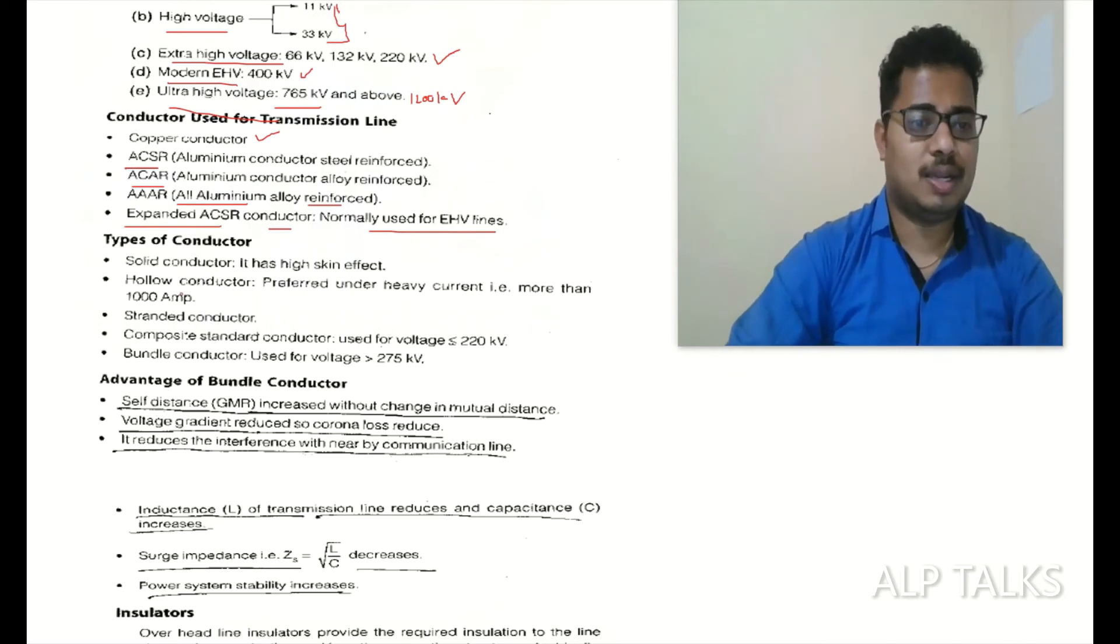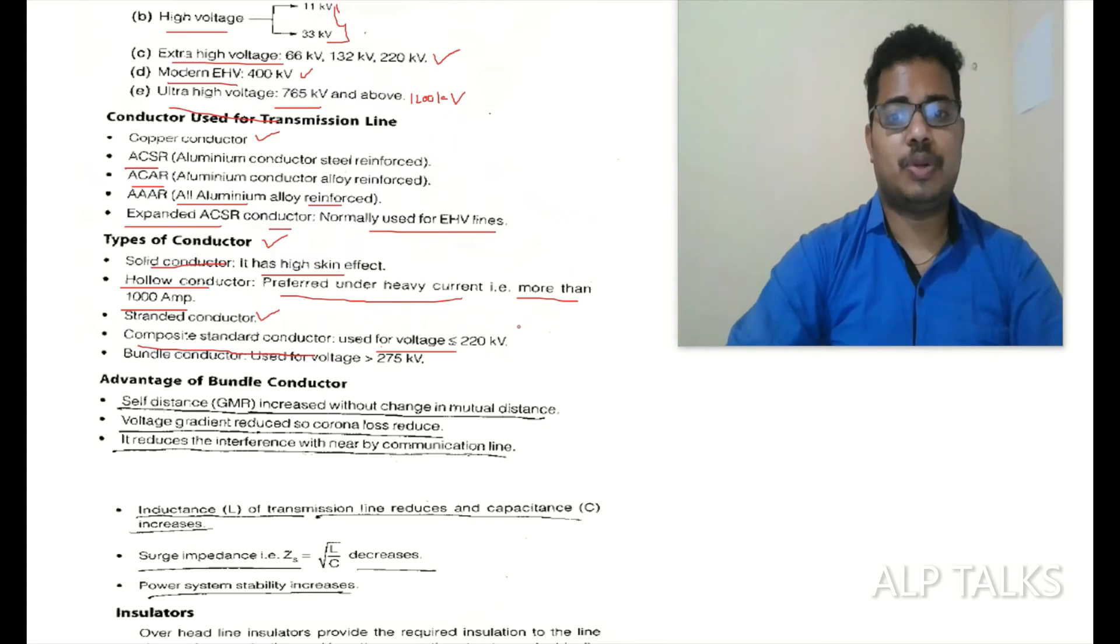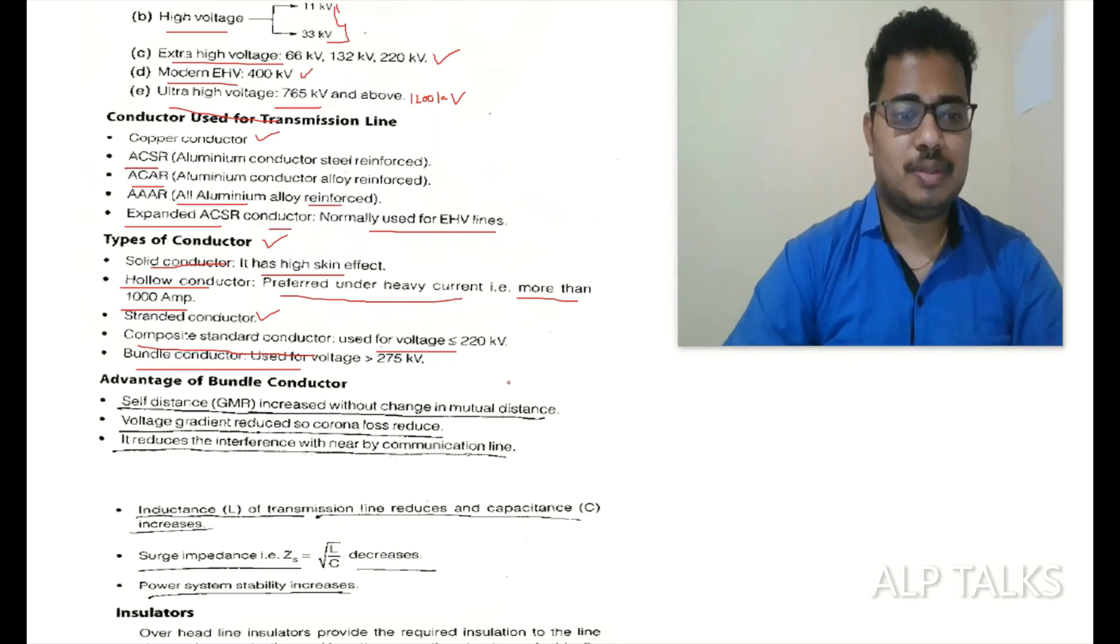Types of conductors: solid conductor - it has high skin effect. Hollow conductor - preferred under heavy current more than 1000 amps. Stranded conductor - composite standard conductor used for voltage less than or equal to 220 kV. Bundle conductor - used for voltage greater than or equal to 275 kV.